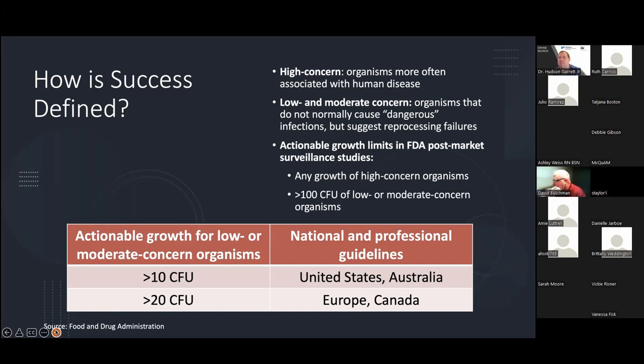So we're not talking about an ideally designed climate here. The reason they had pigeon fecal material was because they had a wall-mounted AC unit in the middle of summer in a high-rise older hospital in New York City, and there was a hole underneath it bringing environmental contaminants in that contaminated the device. Again, the FDA's expectation was a minimal amount, less than 100 colony-forming units of these types of organisms.